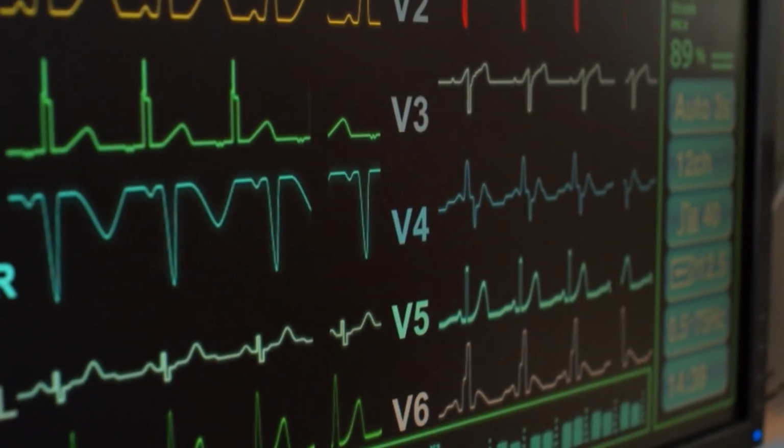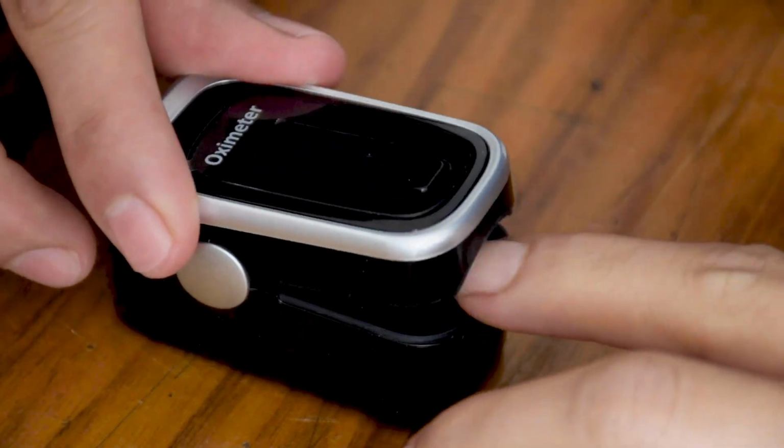And that being said, update your risk management file on all the risk control measures that you have added, right? So to look at an example, a company that makes heart monitors received a report of a device malfunction in certain situations, right? This manufacturer, or your company, would need to investigate these reports and update the risk assessment and risk control measures as needed.